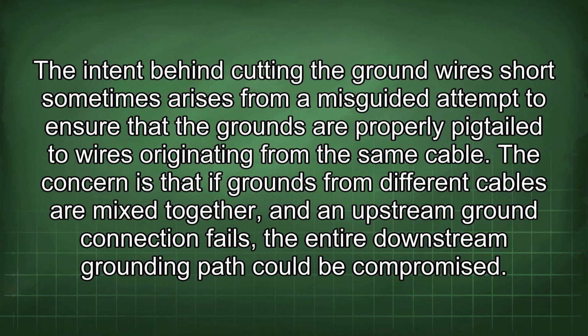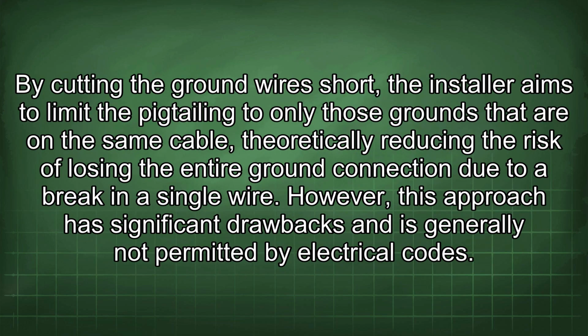The intent behind cutting the ground wires short sometimes arises from a misguided attempt to ensure that the grounds are properly pigtailed to wires originating from the same cable. The concern is that if grounds from different cables are mixed together and an upstream ground connection fails, the entire downstream grounding path could be compromised. By cutting the ground wires short, the installer aims to limit the pigtailing to only those grounds that are on the same cable, theoretically reducing the risk of losing the entire ground connection due to a break in a single wire. However, this approach has significant drawbacks and is generally not permitted by electrical codes.